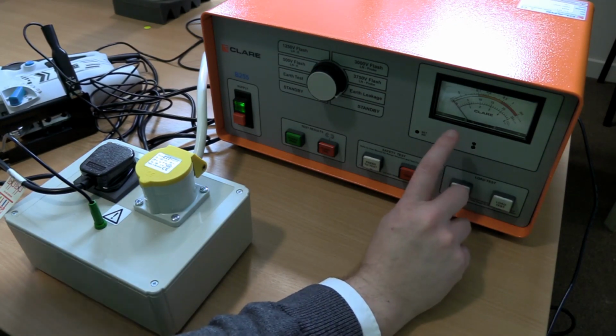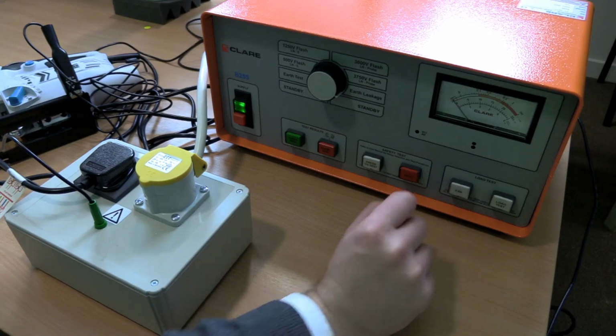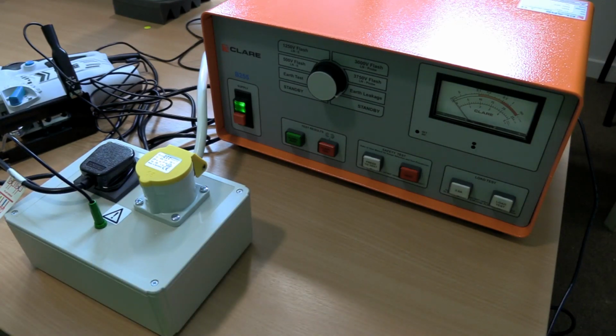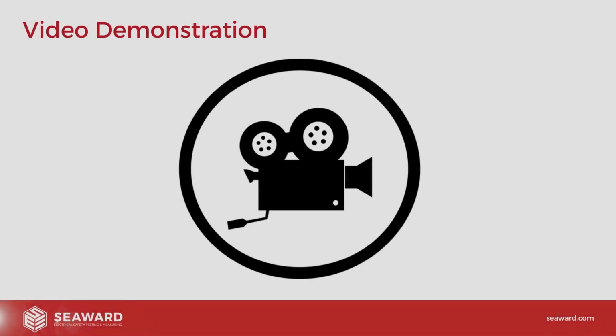So you can see we're getting a very little reading there, showing the touch leakage measurement. Okay, so we're going to move on and talk about the considerations for use, any limitations and reasons for safe use. Now, we have bundled both the considerations and the limitations for both the touch current and the protective earth conductor current, purely because the limitations are one and the same.